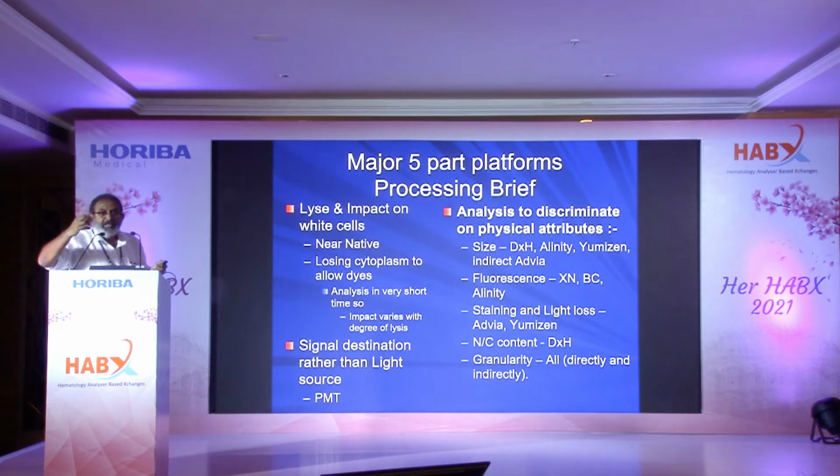So for example, some cell counters will lyse the red cells, will keep the white cells intact, but some lyse will lyse the red cells, and along with that, the white cells will also start shrinking. Then at the same time, they may have PMTs at various angles where it may not pick up what is necessary and what they want is necessary.